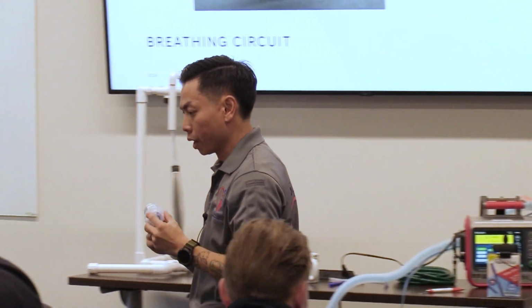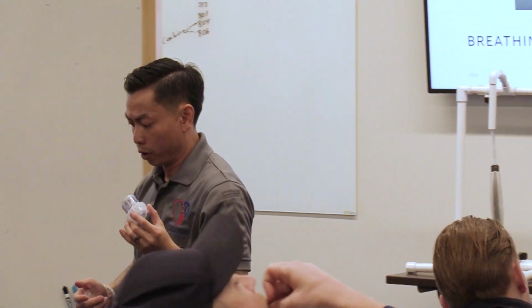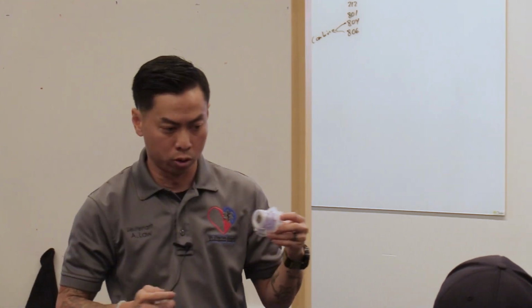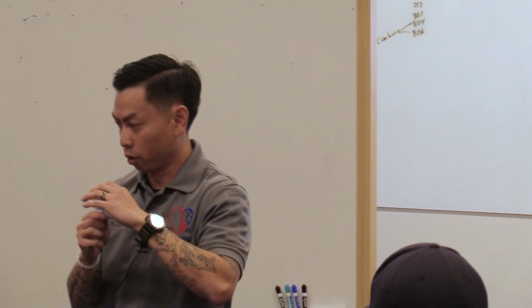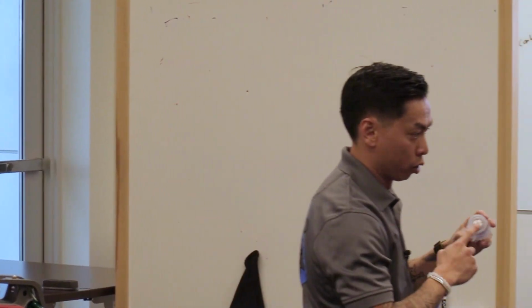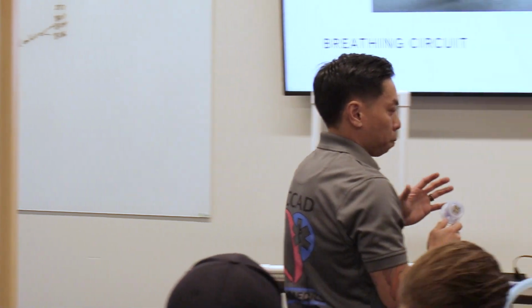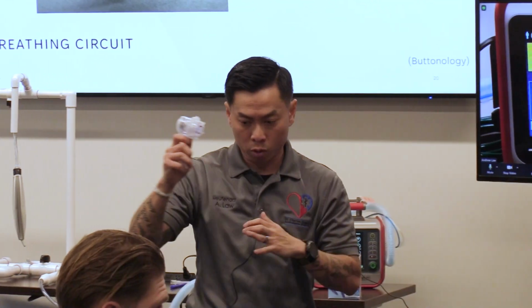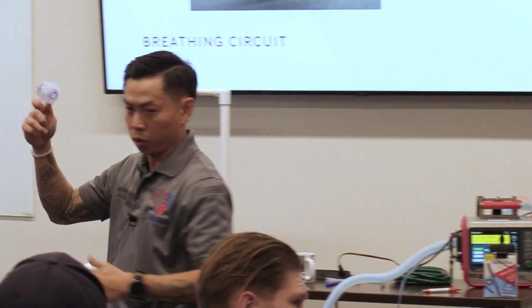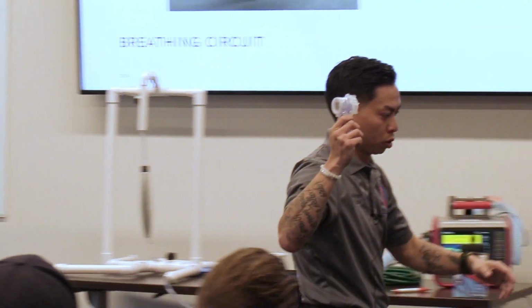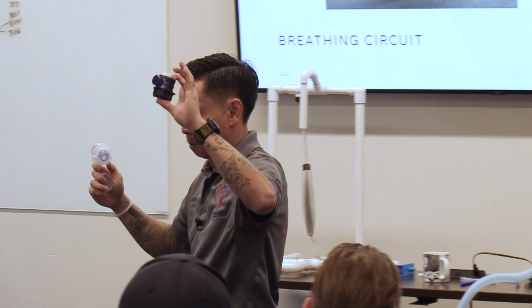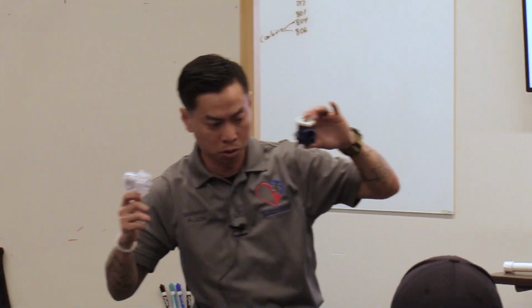So this is a big component of your ventilator. So when you start doing your pre-test, your pre-ops checks, and they're failing, this would be the first part that I would go to, to make sure that rubber diaphragm, everything is intact. The clear ones are intended for one use only. The navy blue ones, which should be on, will eventually make their way to the BC trucks to help support you. These are the reusable ones.